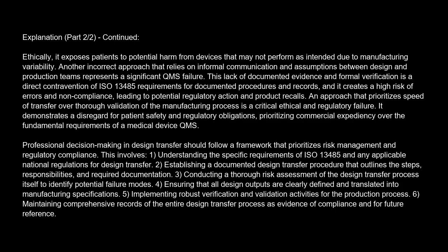2. Establishing a documented design transfer procedure that outlines the steps, responsibilities, and required documentation. 3. Conducting a thorough risk assessment of the design transfer process itself to identify potential failure modes. 4. Ensuring that all design outputs are clearly defined and translated into manufacturing specifications. 5. Implementing robust verification and validation activities for the production process. 6. Maintaining comprehensive records of the entire design transfer process as evidence of compliance and for future reference.